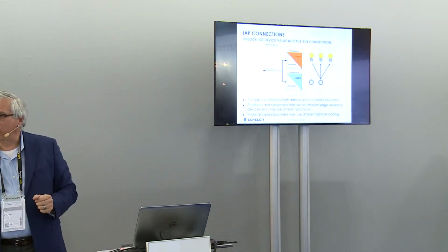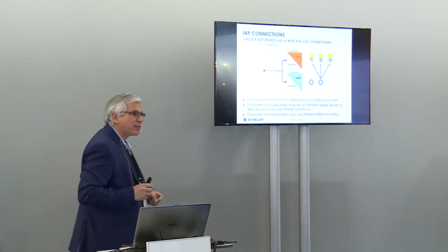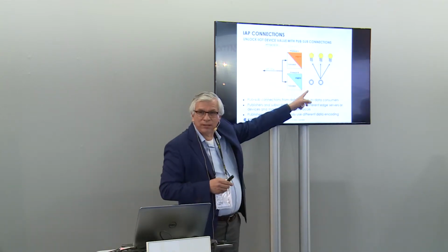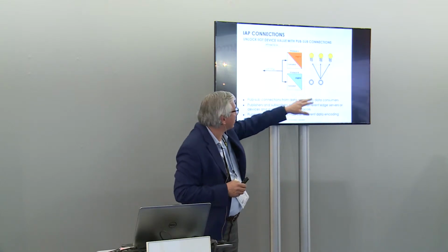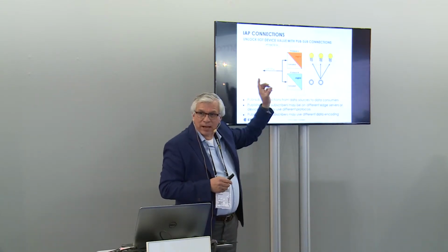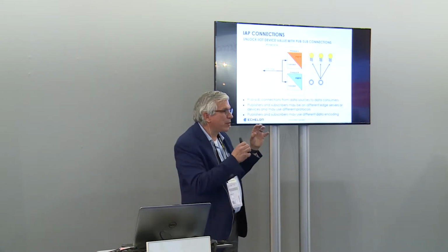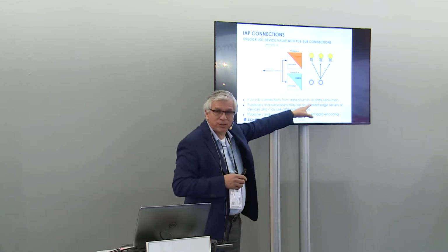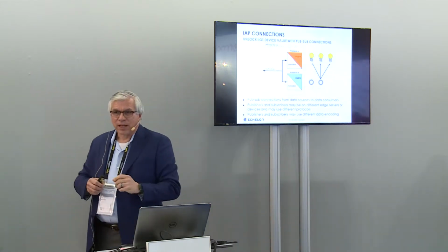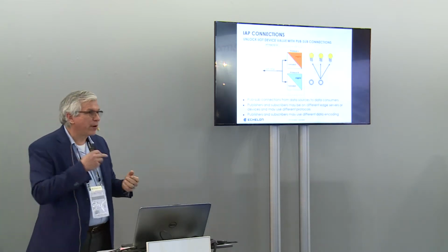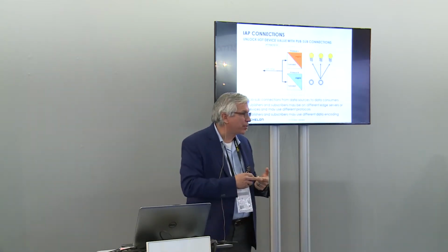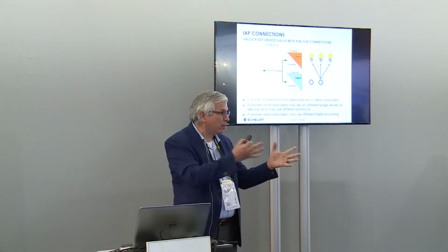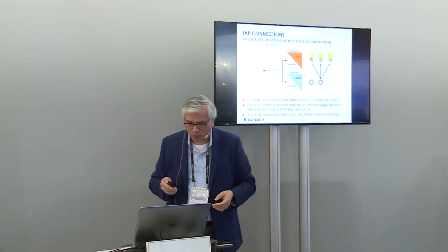But even more interesting is now we can create connections between devices, even devices that are on different networks. So for example, if that's a Modbus sensor and that's a LON lighting control, I could create a connection so that when that motion sensor goes off, the light turns on. And that can happen even across media, even across protocol, even across edge servers. So I may have this on one edge server, I may have that on another edge server. I could create connections between them. So you have very responsive systems with peer-to-peer connections so that you can have the instant response that you want when something like a motion event occurs and you want the lights to turn on.